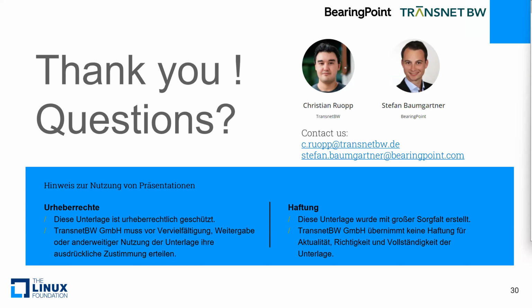Perfect. Next question: is it possible to host this SCL editor for offline web server use without an active internet connection? Yes, for sure. You can use the whole SCL editor without any internet connection. You only have to download it once and bring it via stick or differently onto your computers. There is also a good manual on the wiki of OpenSCD or CoMPAS. So it's possible.